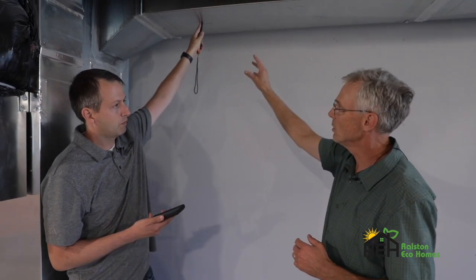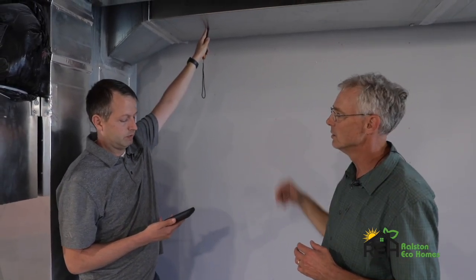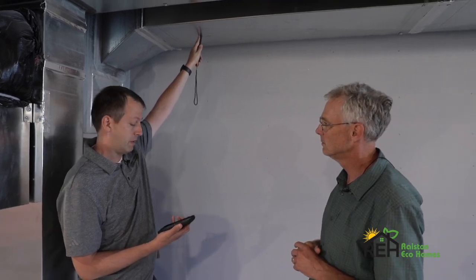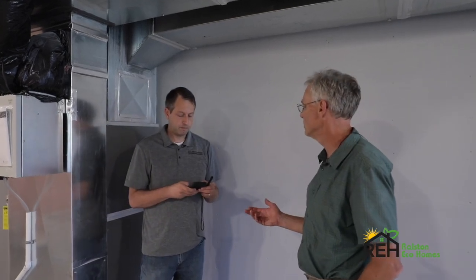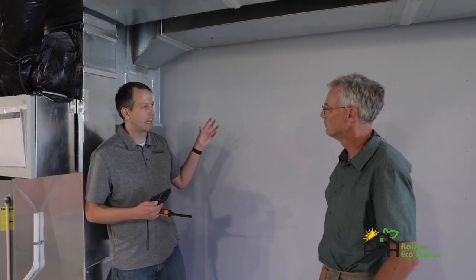So we put a hole in the supply part of the system, and we're measuring the temperature here. Correct. And we're hitting about 55 degrees. So the return air is 68, which is what we predicted it would be, because the house is currently at 70 degrees. And then the air that's going out to the house is 55 degrees. Yep. So that's the differential we would expect. So maybe even a little low. A little low, yep. So if we can get that airflow back up, adjust refrigerant, I think we should be good. Okay, great. Now we're going to look at the individual ducts to look at the airflow at those, so we can balance the system.